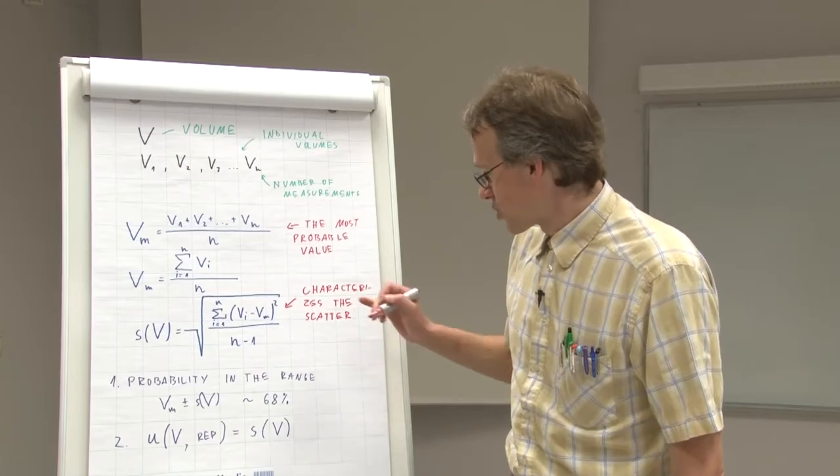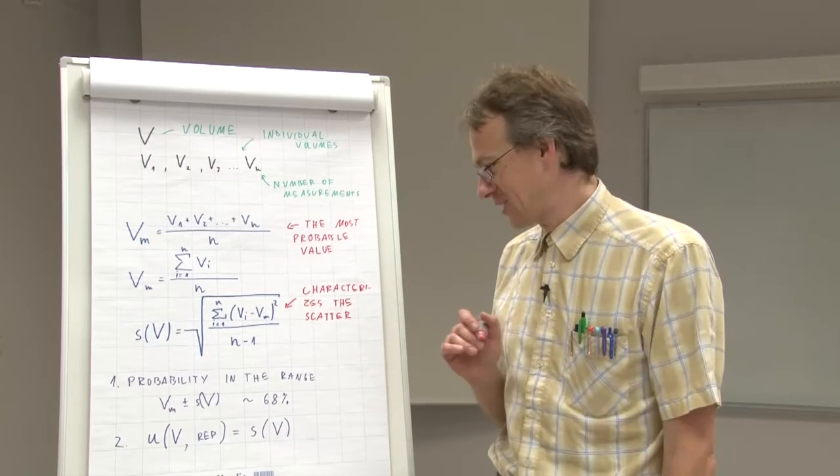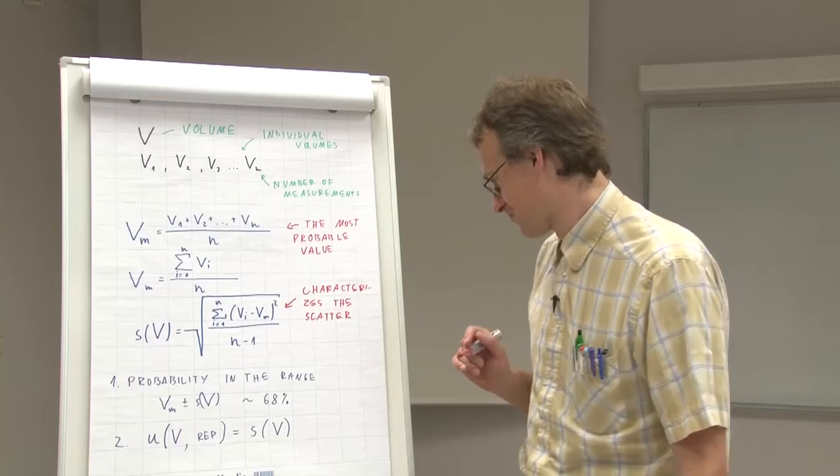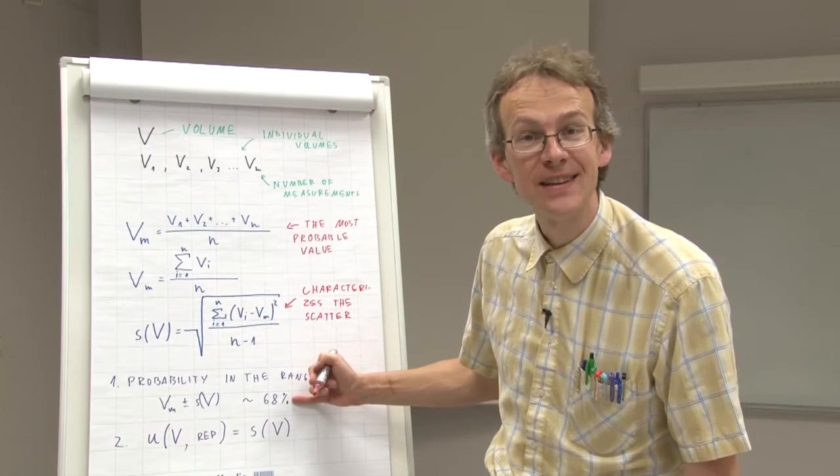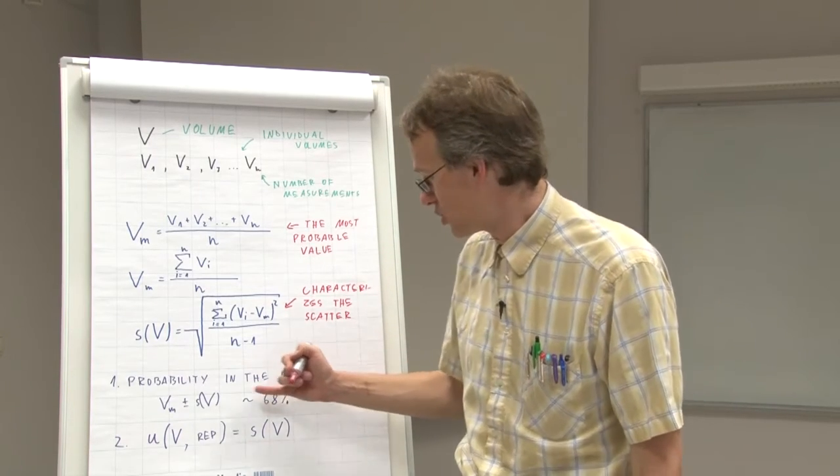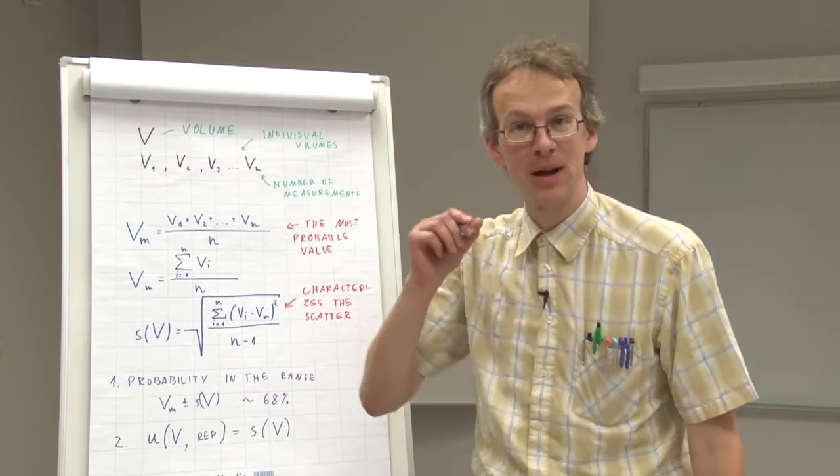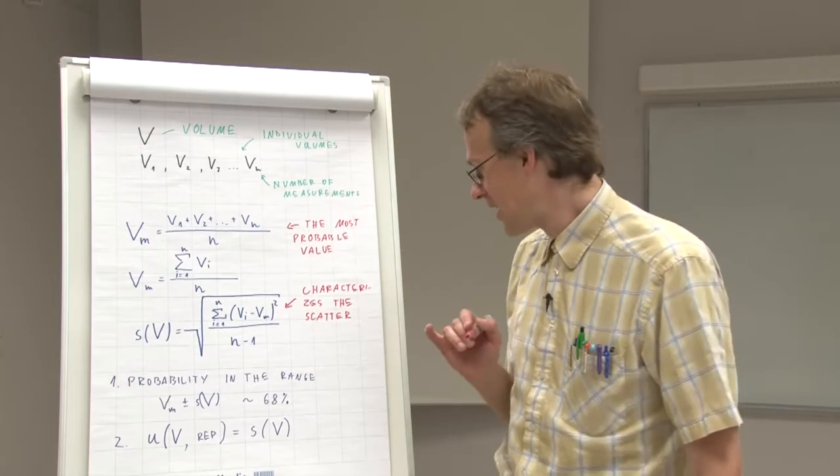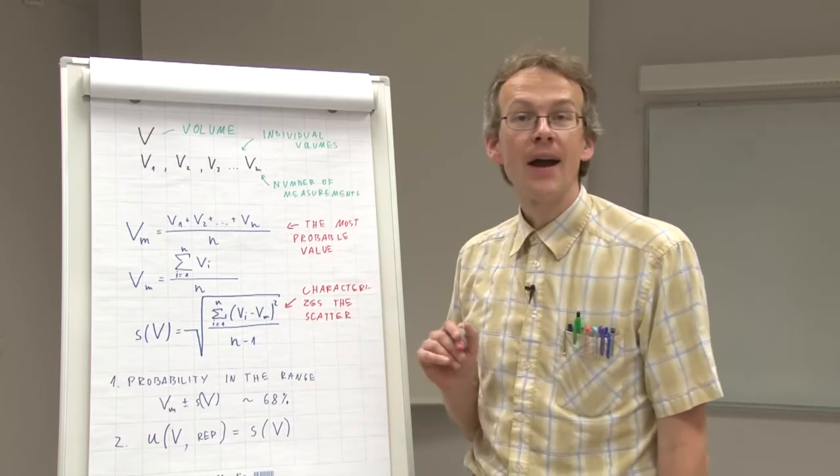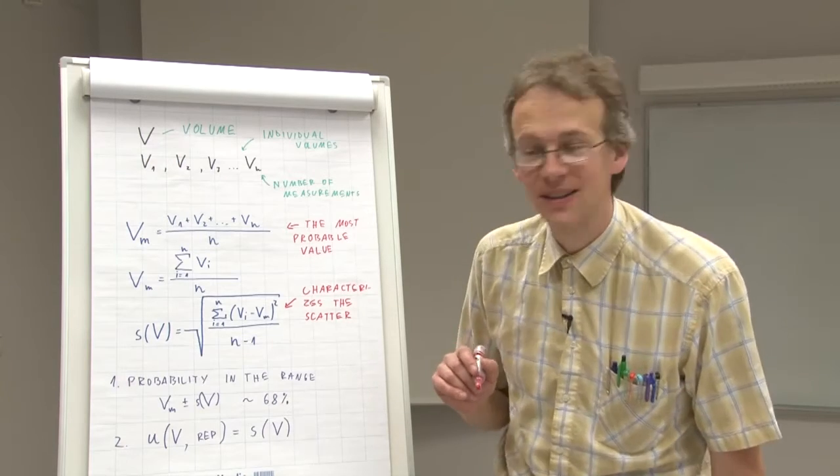The standard deviation carries two important bits of information. On one hand, it defines the range within which the probability of finding the next pipetted volume is roughly 68%. And finally, via standard deviation, we define standard uncertainty.